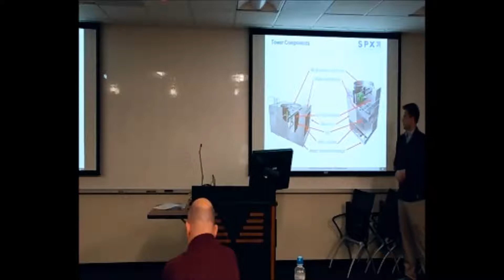Cooling towers are known to be air scrubbers. You basically have a lot of air coming in contact with water, and in Los Angeles, we all know the air isn't so clean out here. So these cooling towers, if not properly maintained, can get pretty dirty. It's good to observe your fill every once in a while and see if it needs to be brushed or cleaned.